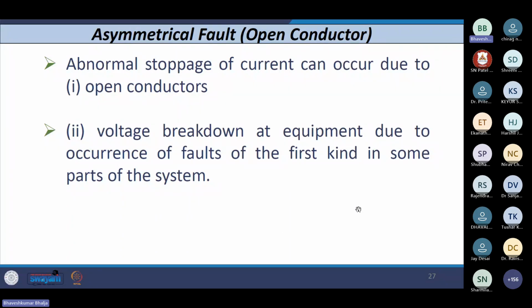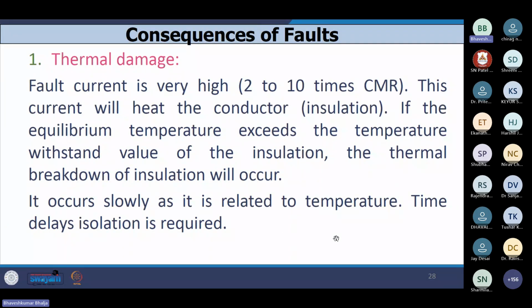So open conductor, we are not bothered about this. Now, whenever a line to ground fault or triple line fault occurs, two things are very important. One is thermal damage, which is related to the deterioration of the insulation. Whenever a fault occurs, the current becomes drastically high, let's say 2 to 10 times the continuous rating of the conductor or any machine. At that time the heat produced is I square RT. So thermal damage is very important whenever a fault is concerned.